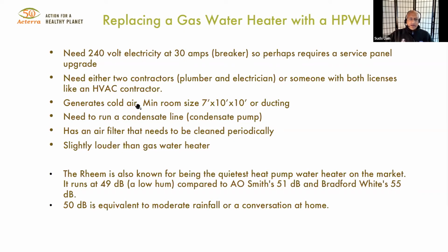It generates cold air, so if you're putting it in a place where you don't want the cold air, you have to vent it to the outside. If you keep it in a room, the room has to be at least 7 by 10 by 10 feet to create enough heat. Otherwise the room will cool down so much that the heat pump won't be able to extract heat from that air. So you need a room of a certain size, or duct it to the outside. If you're putting it in the garage, that's pretty much the perfect place. That's where most people have their heat pump water heaters.